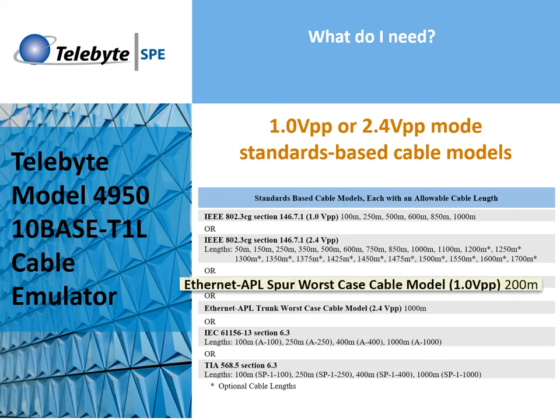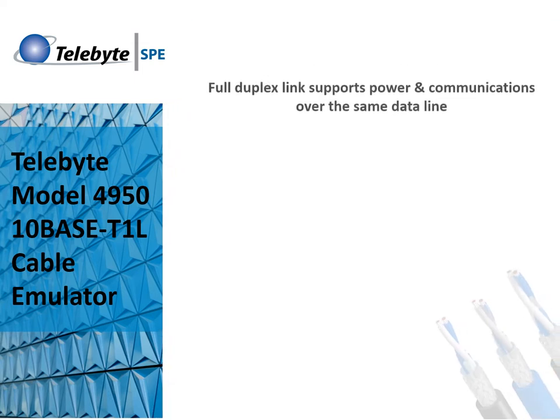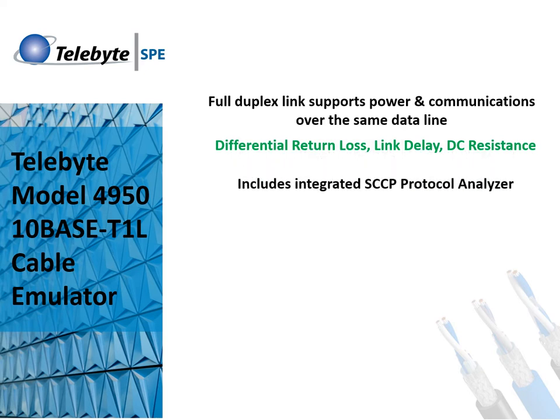Our example today will emulate the Ethernet APL Spur worst case cable model at 200 meters. Features include a full duplex link that supports power and communications over the same data line, differential return loss, link delay, DC resistance, and an integrated SCCP protocol analyzer.